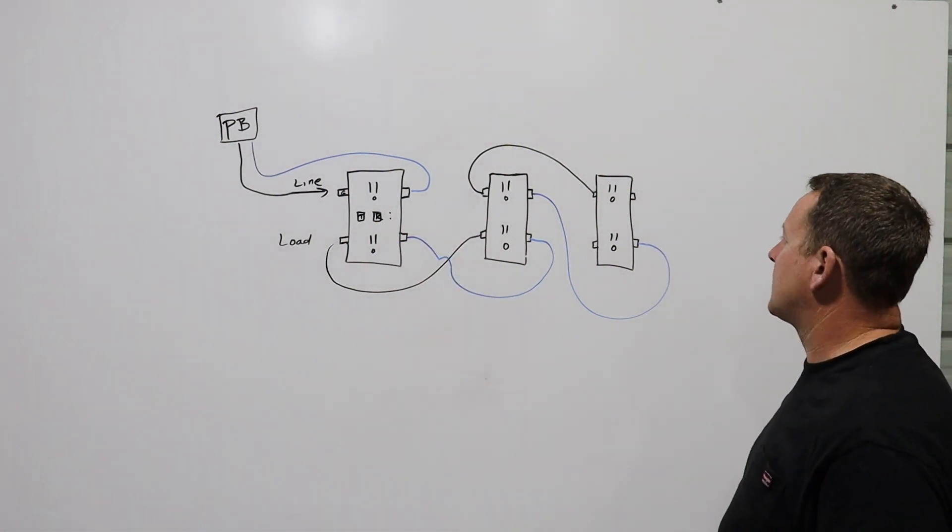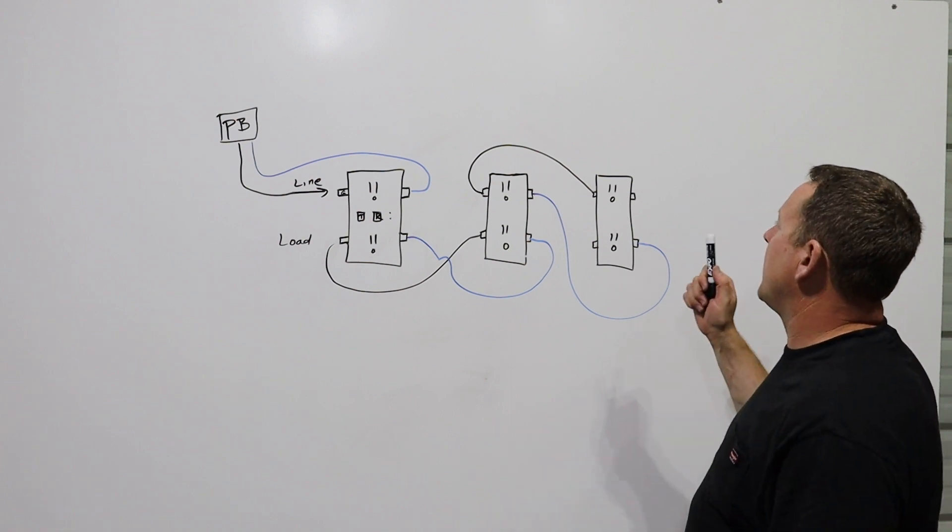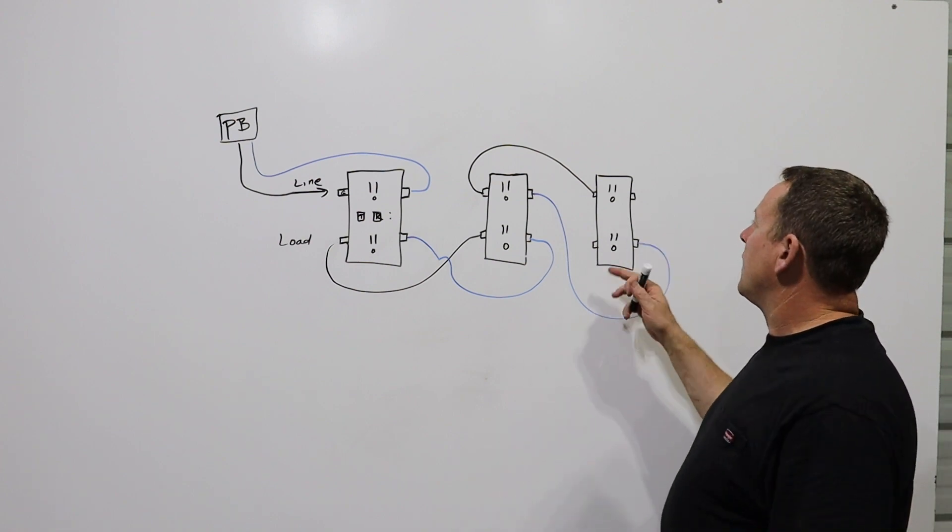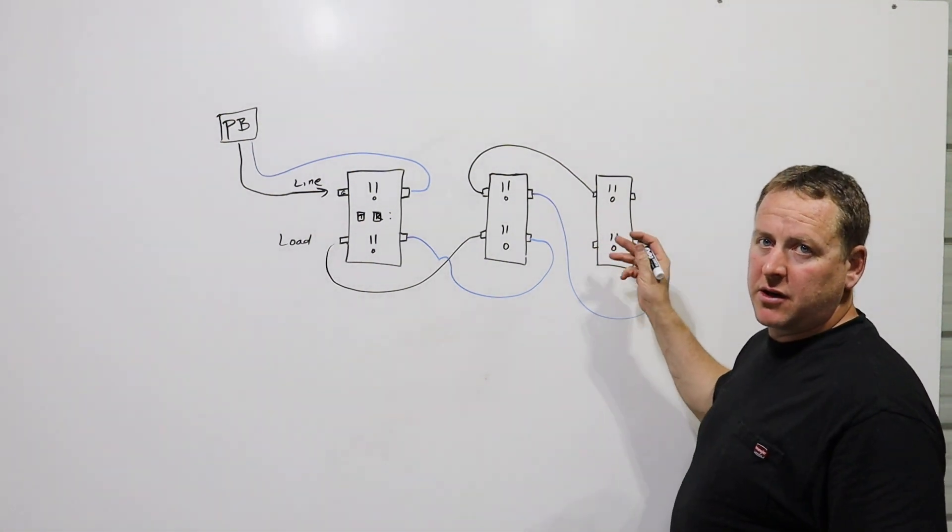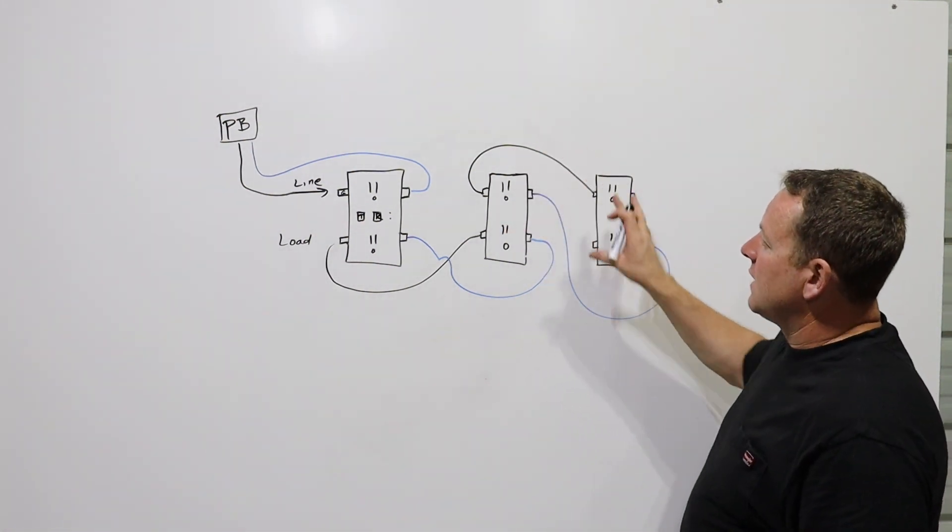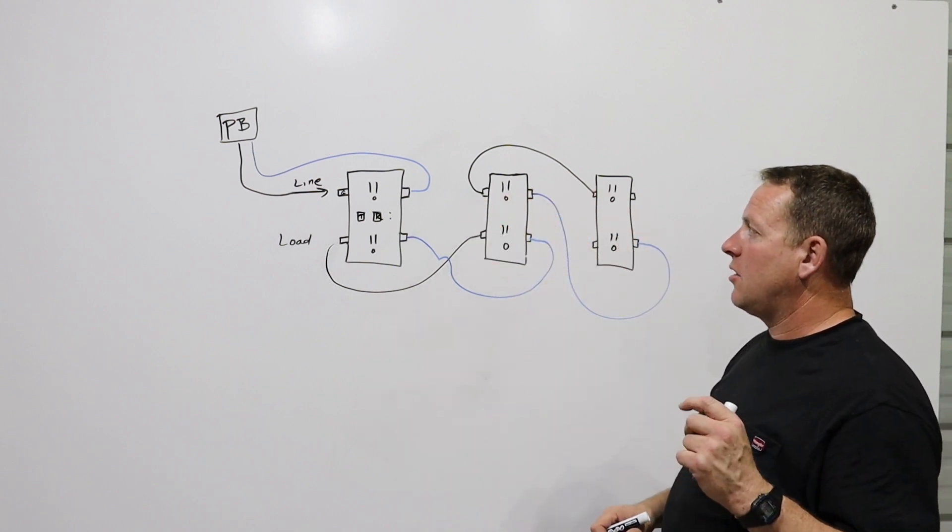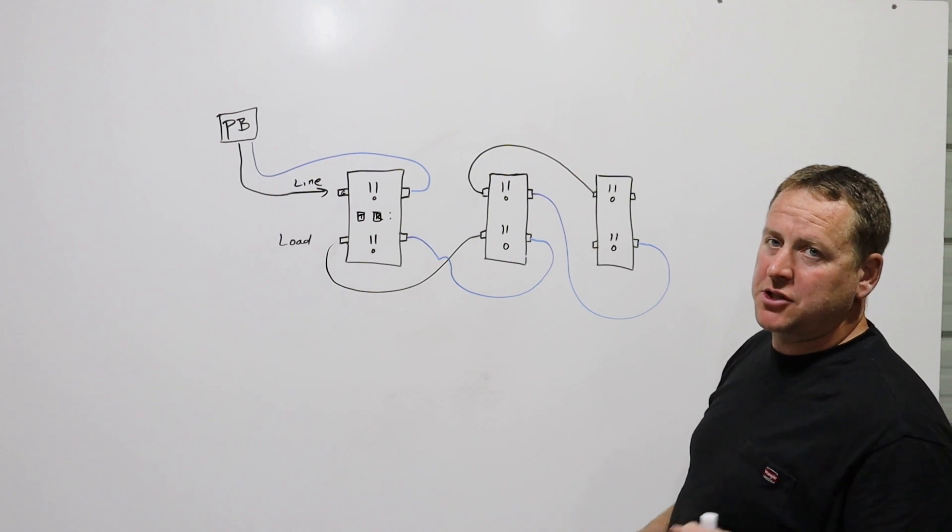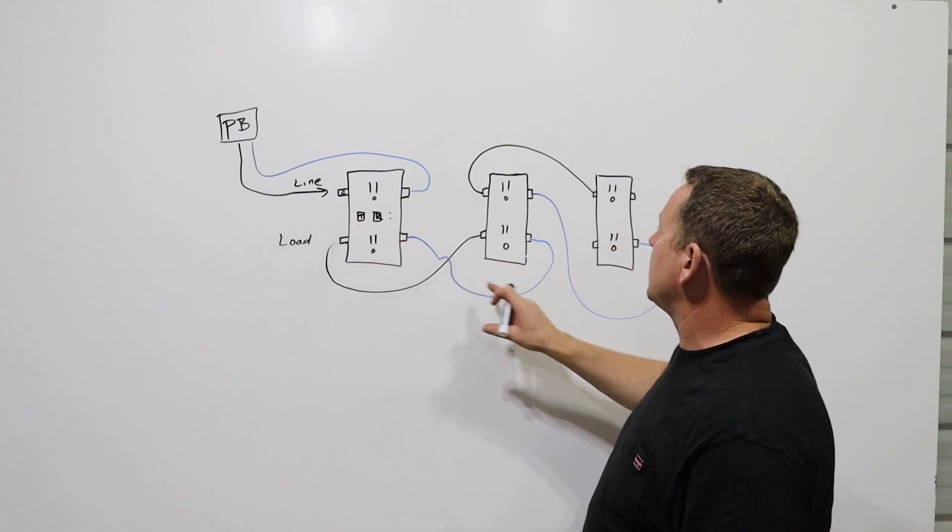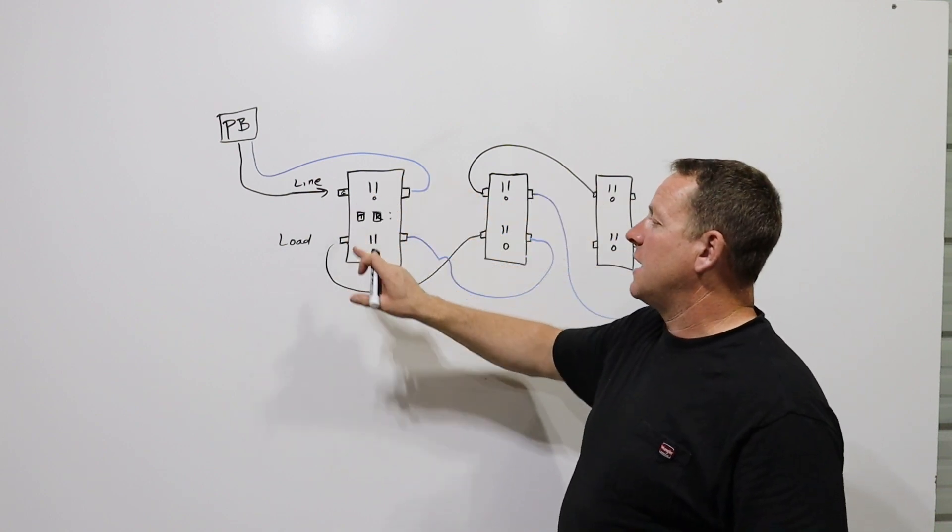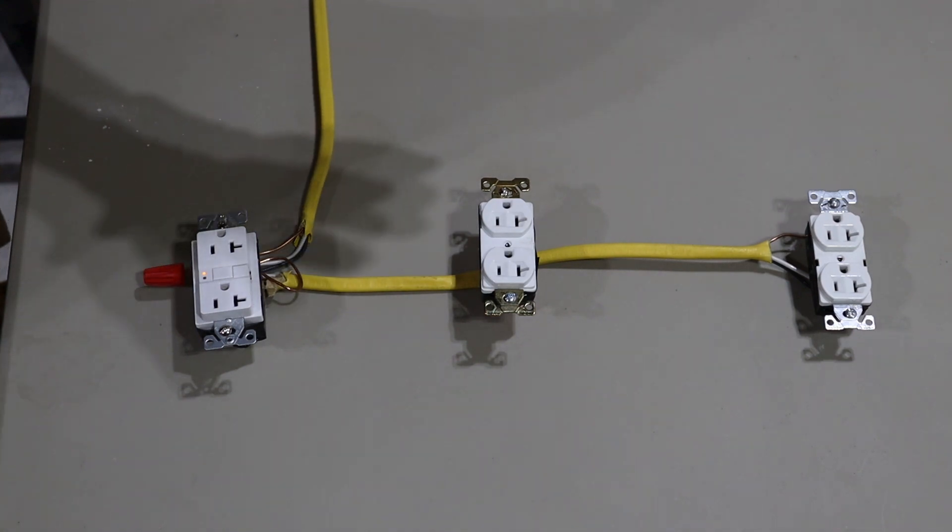Now, your little brother walks in with a knife, butter knife hopefully, and sticks it in the outlet. Sticks on the hot side of this outlet that is not a ground fault circuit interrupter outlet, but it's within the circuit. He sticks a knife in there, and almost instantaneously, he doesn't get shocked. The ground fault circuit interrupter says, hey, something's wrong somewhere on this circuit, and it still trips.